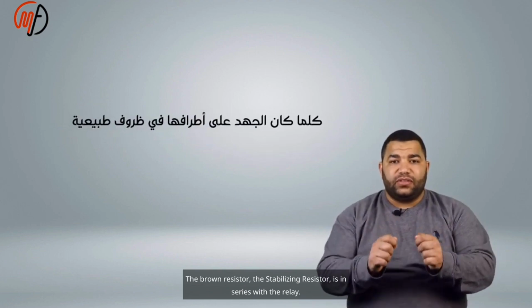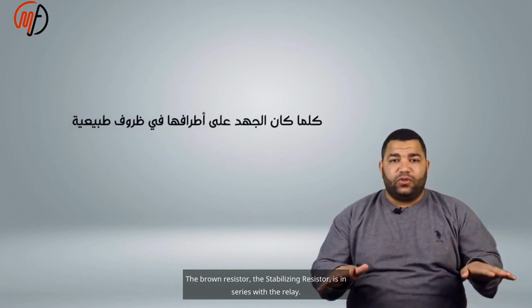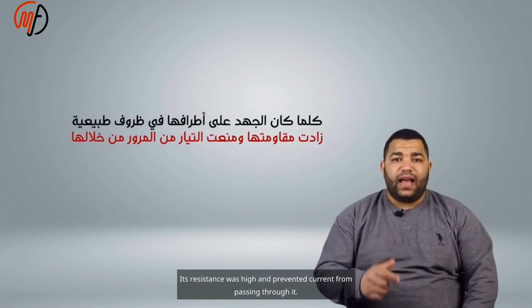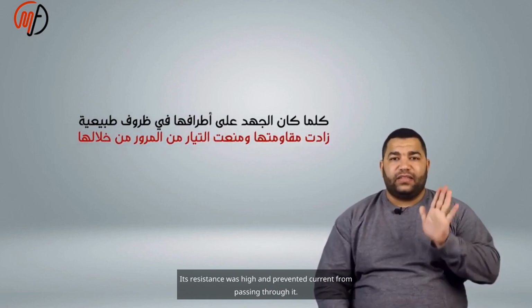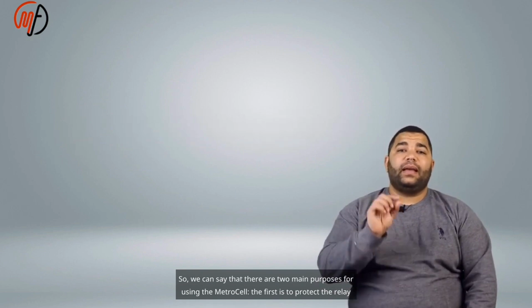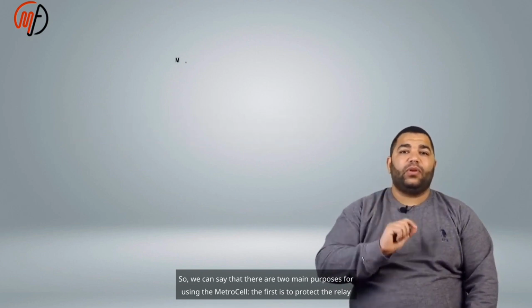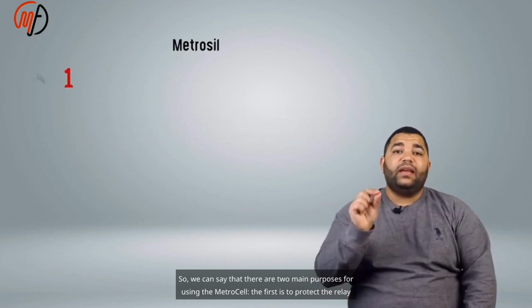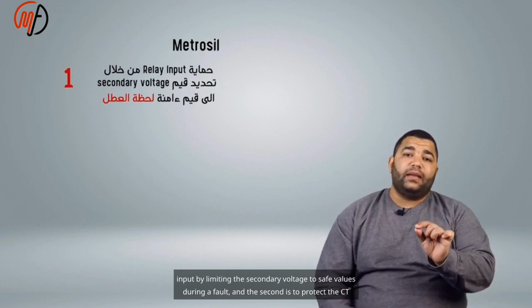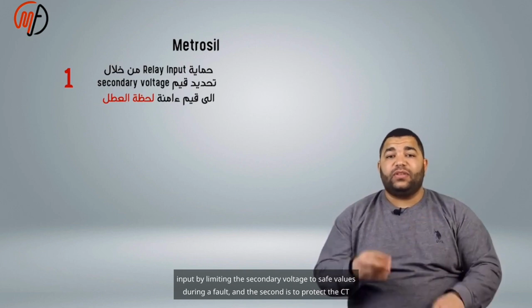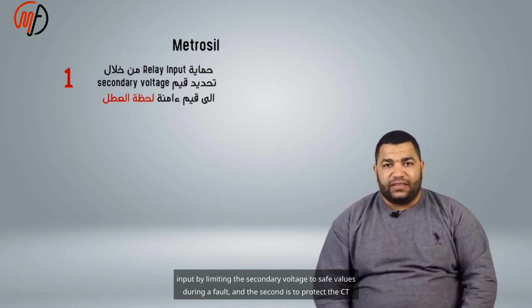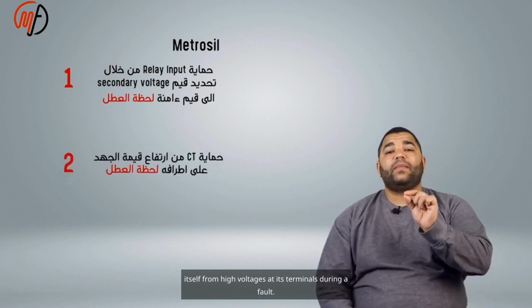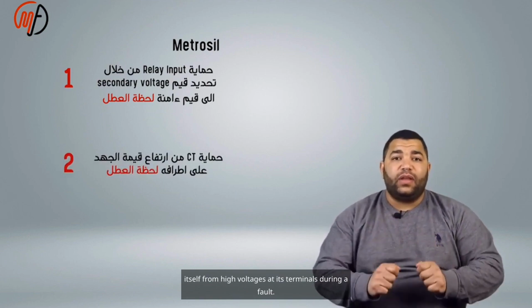The brown resistor, the stabilizing resistor, is in series with the relay. Its resistance is high and prevents current from passing through it. So we can say that there are two main purposes for using the Metrosil. The first is to protect the relay input by limiting the secondary voltage to safe values during a fault, and the second is to protect the CT itself from high voltages at its terminals during a fault.